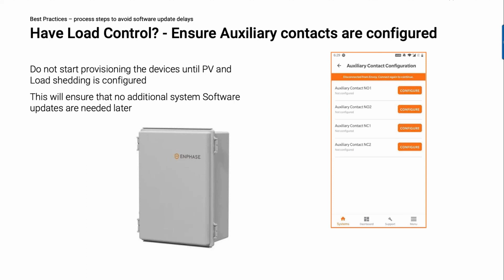Next best practice, if you are installing load control. This is a load control box from Enphase. Load control sheds off loads that could collapse the microgrid. If you're installing a load control device and you start to provision the system, you want to make sure that you actually configure how these load control contacts are supposed to be configured. That is in the installer app. There is a screen to configure your auxiliary contacts.